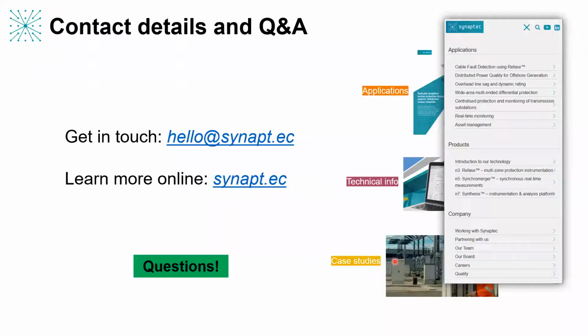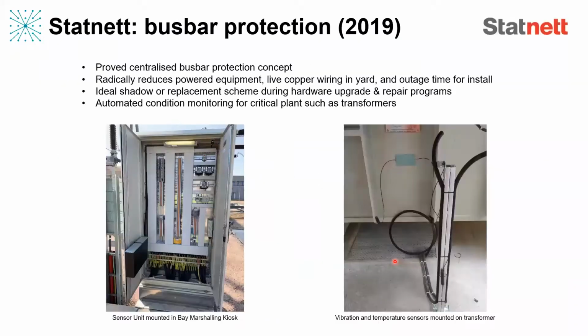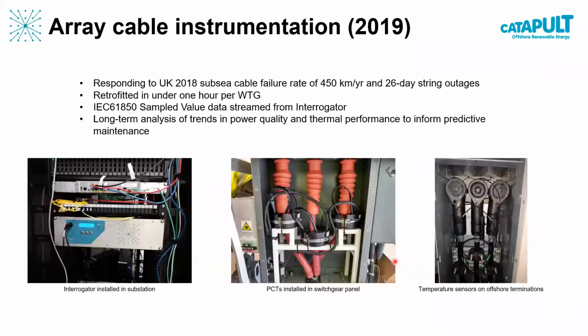Philip, I'm going to throw you under the bus at the beginning here. I don't know if you've got the backup in this slide deck, but some people were asking for some pictures of the sensors again, so they could understand what we're looking at. So what's this idea of a standard CT, and what does it look like, and how are we doing this secondary connection to a standard CT? It'd be maybe useful if you could go back over that. This perhaps is a useful slide on that. So the three photographs here are from one of the early offshore installations. In the middle installation, you can see the phase cables from the offshore turbine coming up through the floor and being split into individual phases.